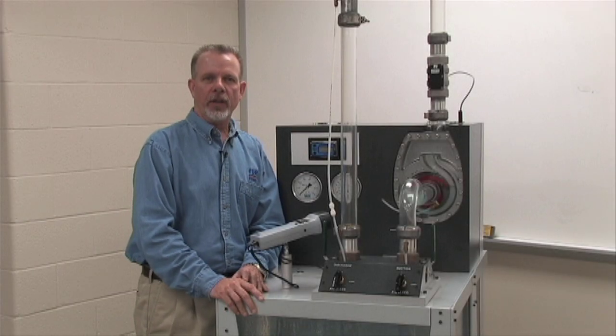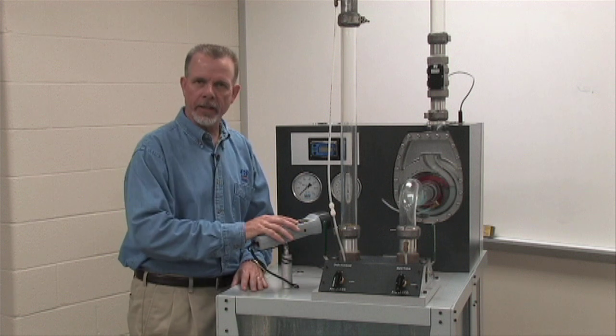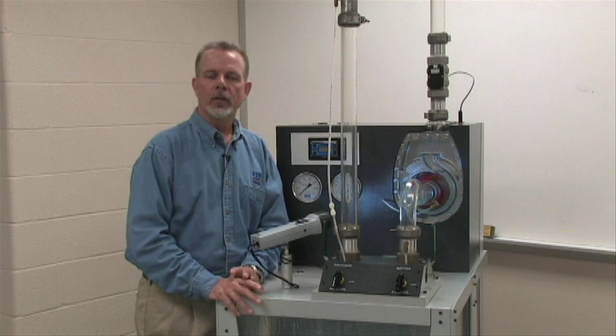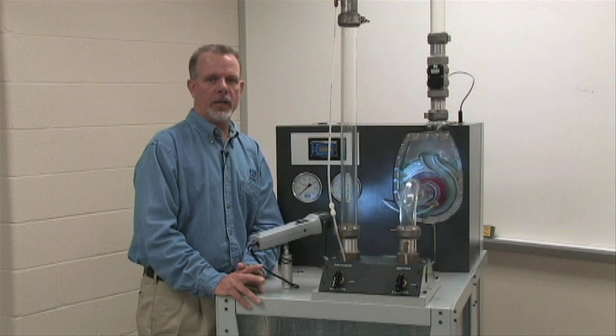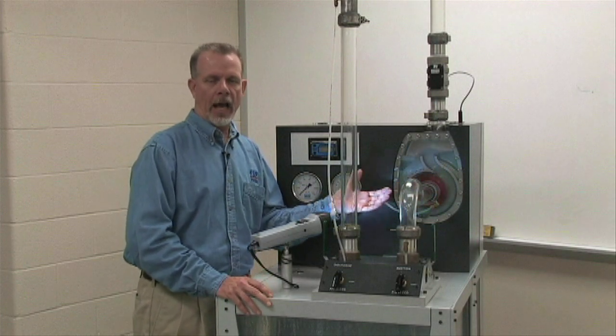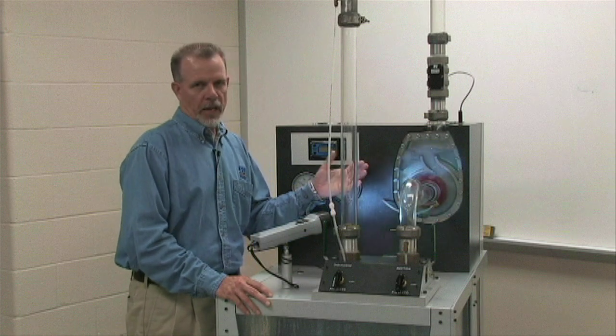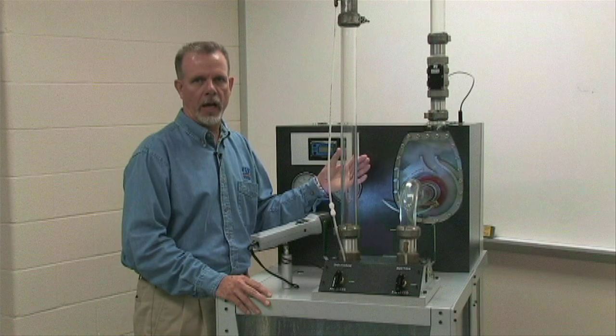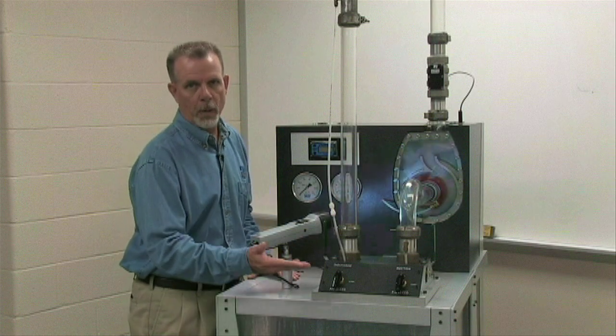As you know from the previous video, water must recirculate inside the volute casing. During this recirculation process, there is a low pressure created at the eye of this impeller. Because atmospheric pressure outside is higher than the low pressure inside, water is forced up the suction pipe.